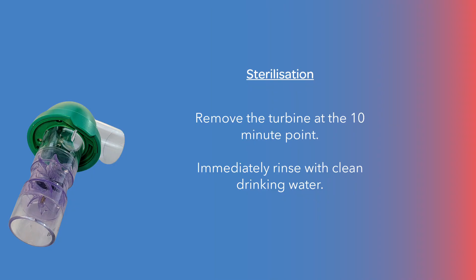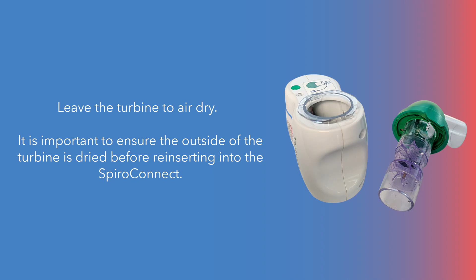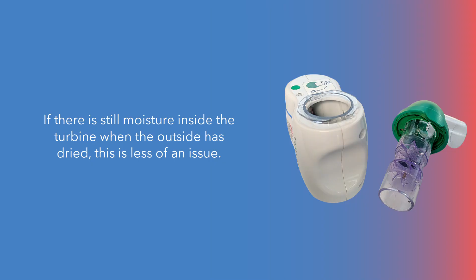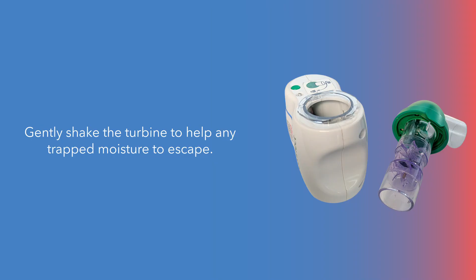Remove the turbine at the 10-minute point. Immediately rinse with clean drinking water. Leave the turbine to air dry. It is important to ensure the outside of the turbine is dried before reinserting into the SpiroConnect. If there is still moisture inside the turbine when the outside has dried, this is less of an issue. Gently shake the turbine to help any trapped moisture to escape.